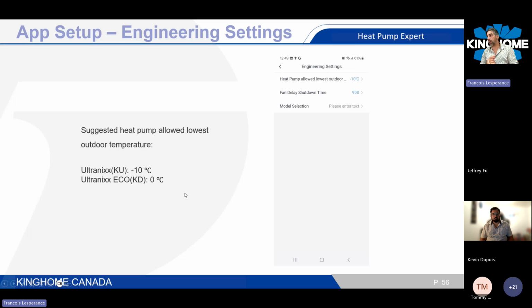We suggest for the heat pump that you adjust your balance point for a KU to about -10, and we will suggest for a KD about 0 degrees Celsius. But it's up to you to adjust it. Some customers, if you have a KD unit installed, maybe want to have the balance point at 5 degrees Celsius or 3 or whatever. So the system will switch over to the furnace at that point.